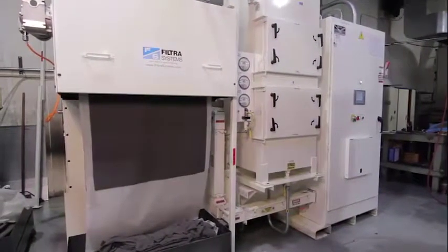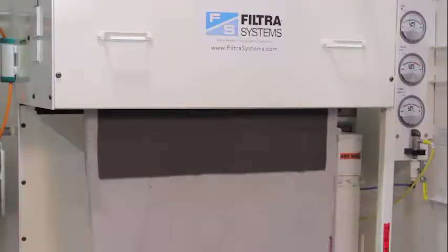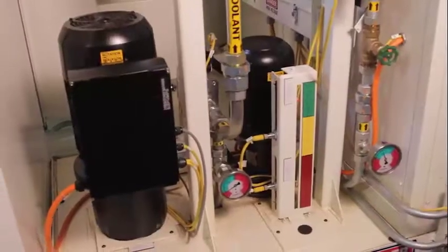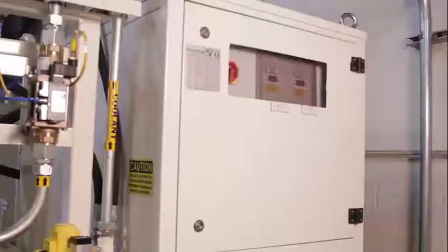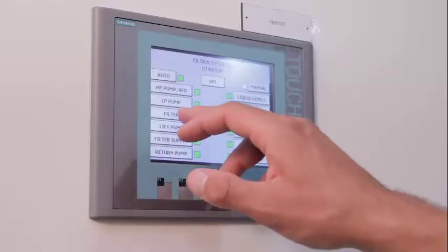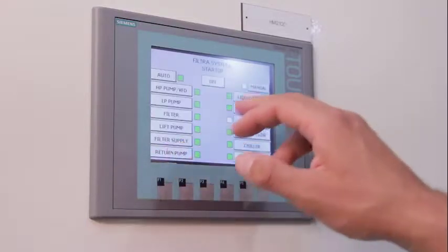The standard PV50 has a coolant and oil filtration module which includes a drying station where the maximum amount of oil is removed from the filtered swarf prior to discharge, CNC supply pumps, mist collector, spindle and cutting fluid chiller, and PLC control panel to provide the CNC machine tool with a single interface for the required utility.